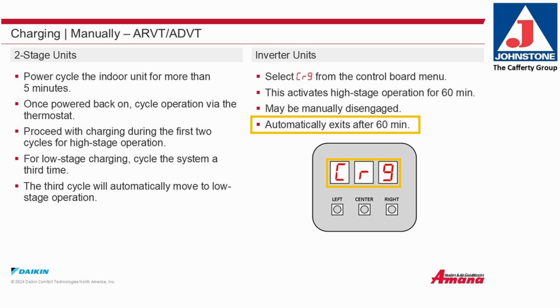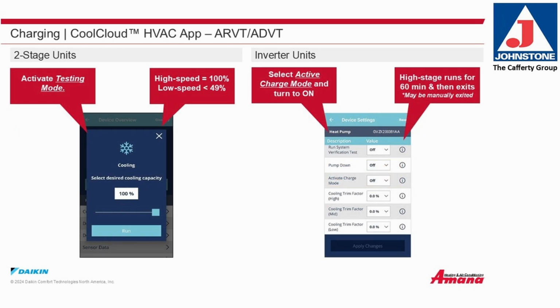Charging using the CoolCloud HVAC app. On 2-stage units, activate testing mode. High speed 100%, low speed 49%. On inverter units, select active charge mode and turn to on. High stage runs for 60 minutes, then exits. You may also exit manually.